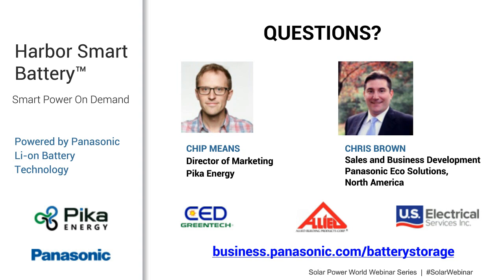Okay, perfect. Can we use this energy system for peak shaving applications? Yeah, so one of the modes I mentioned before, you can basically tweak the thresholds for self-supply and use that as a way of avoiding those peak events. One of the things that we expect to add on the roadmap for the Pika Energy Island system is time-based and predictive peak shaving. So something more sophisticated for those commercial applications where you'd be trying to watch those peaks and offset them. As it is now, if the customer knows their threshold, you can adjust the inverter to have the threshold met by the battery as opposed to through grid power, and that's basically a way of doing what we call peak avoidance. So similar application, but not what you'd consider traditional peak shaving.